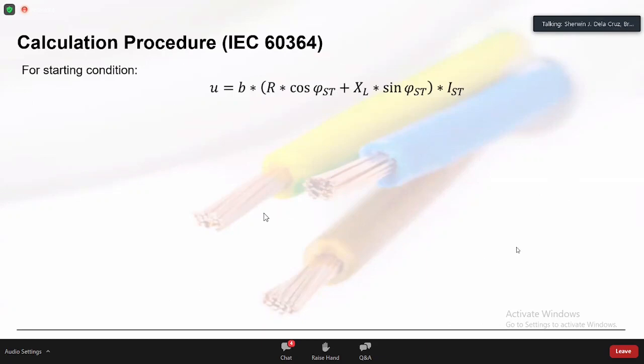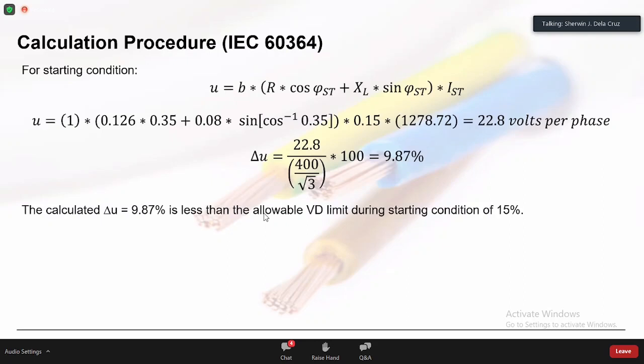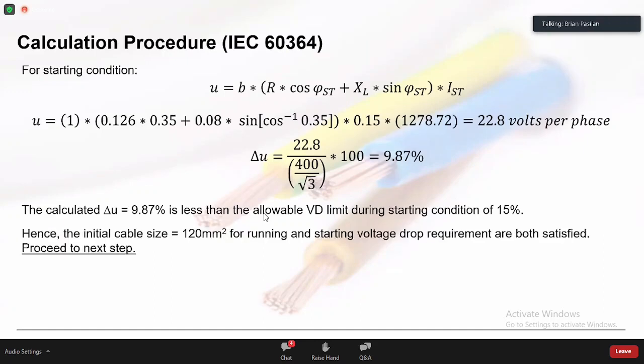Step 4 continued — verify voltage drop during starting conditions. Using starting PF = 0.35 and starting current = 1,278 A: small u = 22.8 V/phase. Percentage voltage drop ΔU = 22.8 / (400/√3) × 100 = 9.87% — which is less than the 15% starting limit. Starting condition: passed. The 120 mm² cable satisfies both running and starting voltage drop requirements.